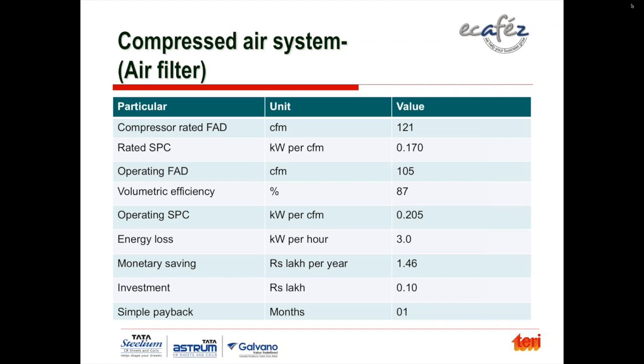That was the rated. But the operating efficiency of the air compressor, which was measured, was found to be 0.2 instead of 0.17, and the compressor was operating at 87% loading. That is the loading. Because of the pressure drop in the air filter, an energy loss of about 3 units was taking place every hour, translating into almost 1.46 lakhs of energy cost implication. That was saved by replacing the air filter.